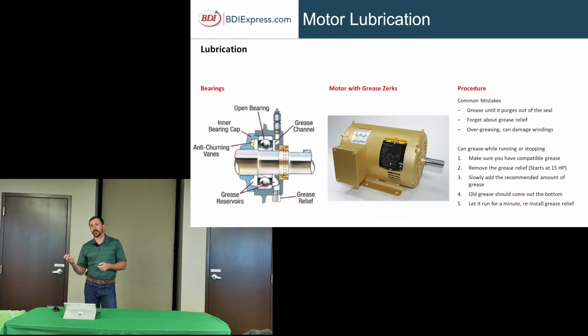And then also forgetting your grease relief. And over greasing can cause damaged windings. And you can grease while it's running or stopped. If it's running, just make sure it's safe. Like Tim said, there's a lot of hazards from fast moving equipment.